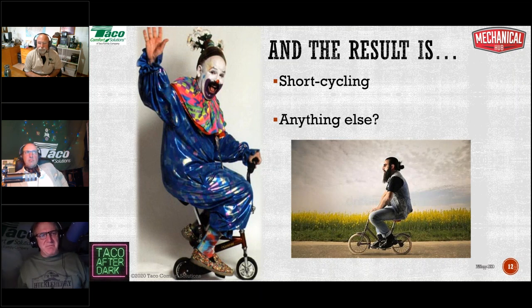Yeah, it's 50% load. And we spend 50% of the heating season at 1/3 load or less. So at least half of the heating season, we're going to have delta T's less than 5. Oh, well, it has to be that way. No, it doesn't have to be that way. Is there any benefit to having it that way? No, not really. It doesn't need to be that way. We can certainly stretch it out, and there's advantages to stretching it out and not short cycling.